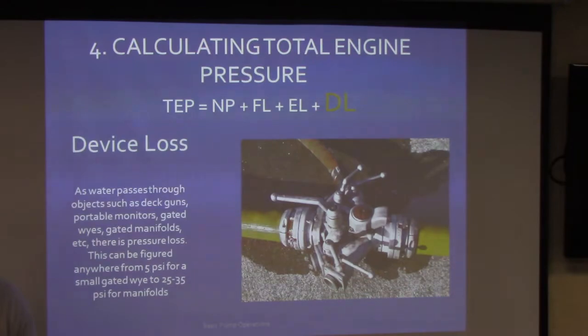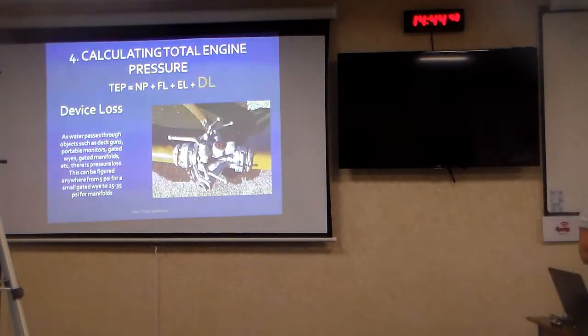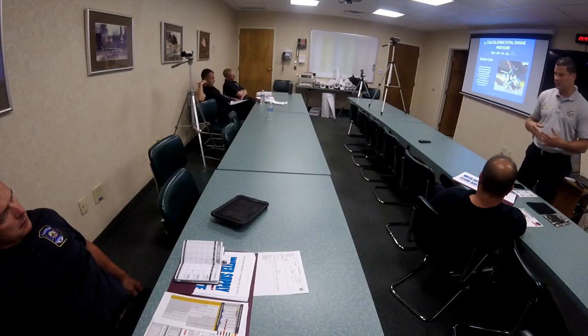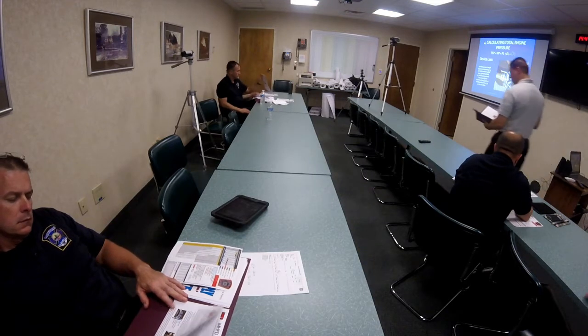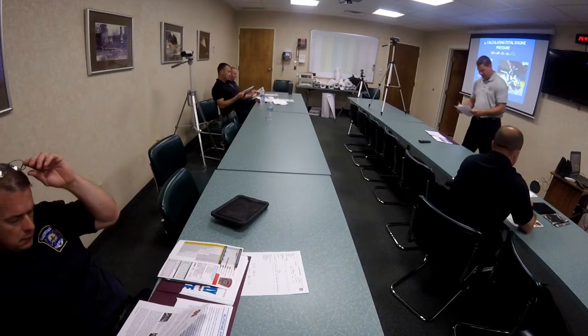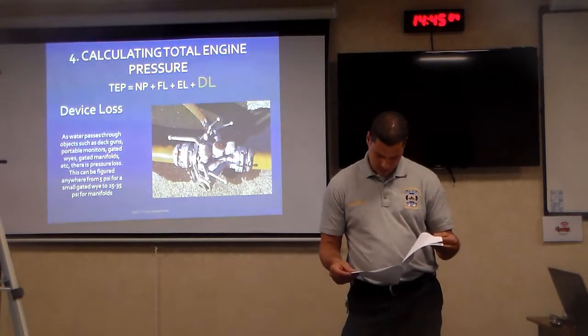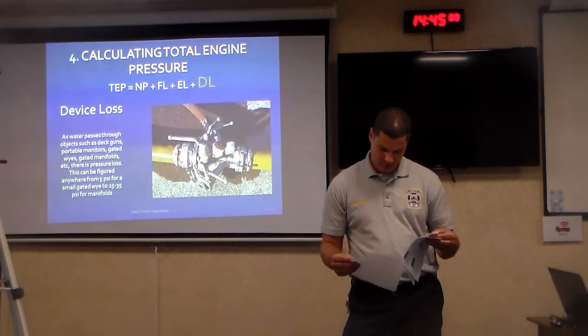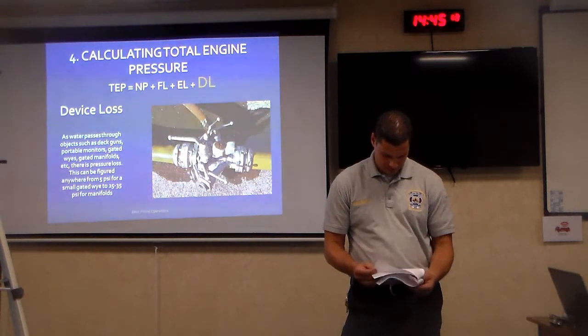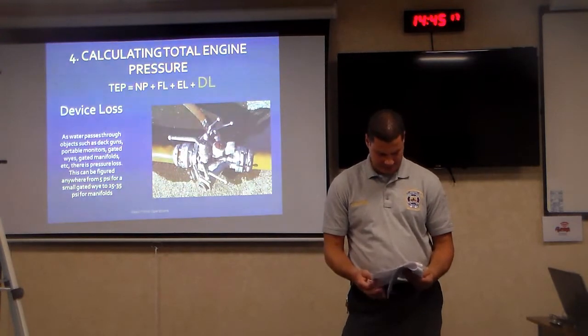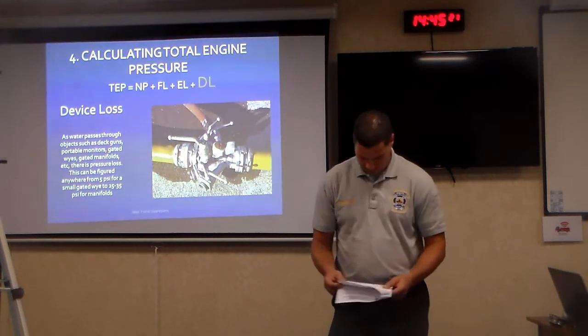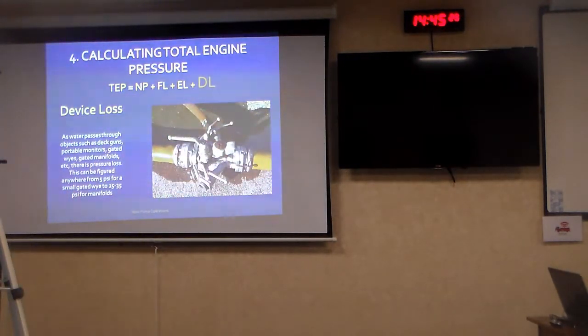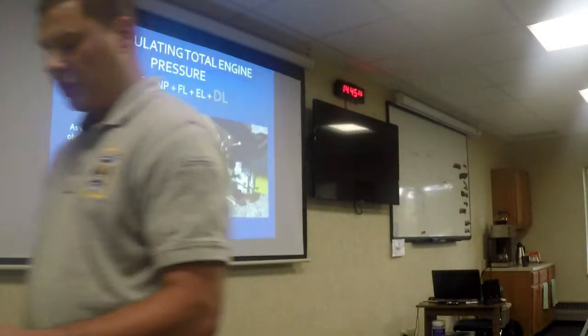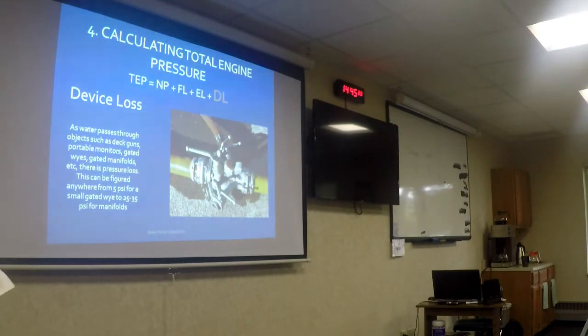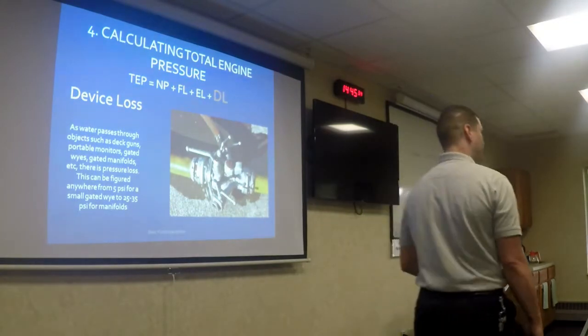Okay? Now, when we talk about device loss, you'll see it in your handout for 31's hydraulics. So go ahead and pull that out for a second, because sometimes device loss gets lost in our calculations because it doesn't usually come up. It should be on the third page at the bottom. For flows up to 1,000 gallons per minute, you should be using at least 25 psi. Okay? What does the next sentence say? Greater than 1,000, 50 psi. That is a lot of device loss.